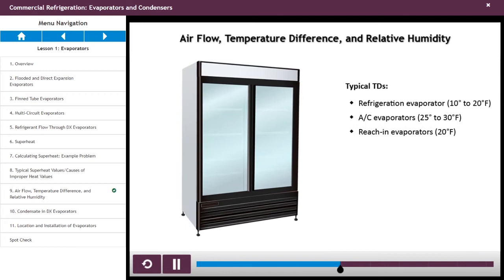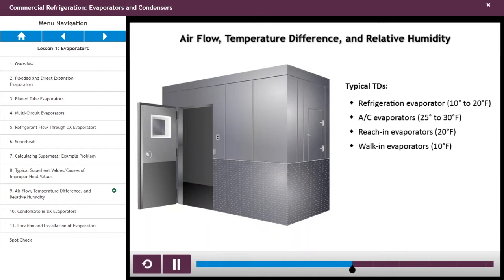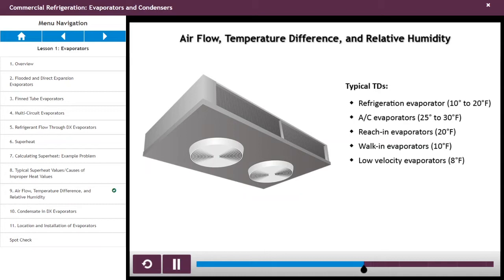Reach-in evaporators have a TD of 20 degrees Fahrenheit, and walk-in evaporators have a TD of 10 degrees Fahrenheit. Some low-velocity evaporators have a TD of 8 degrees or less.